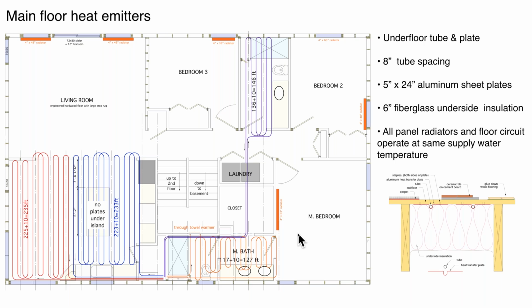Yep. Interesting. Good question and good observation. This was done because honestly, the bed and the 2 nightstands that went in there were huge, and we were not able to put that panel. I would have preferred the panel over here, but because of the furniture layout, there's just no way to do that. And with these R values in the wall, quite honestly, I don't perceive any comfort difference. So you can put a panel radiator on an interior wall. Normally, we like exterior walls if possible, but again, we looked at this. We actually put scale representations of the bed and the 2 nightstands and found there's just no good way to make that fit in that room with that radiator up in this area here.